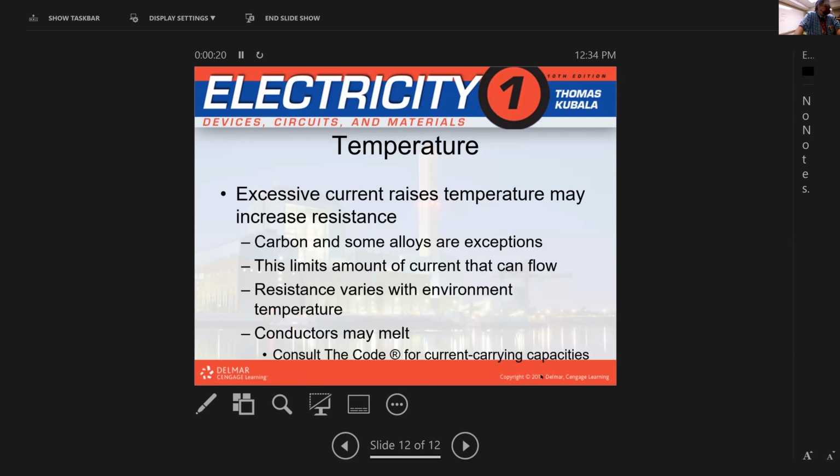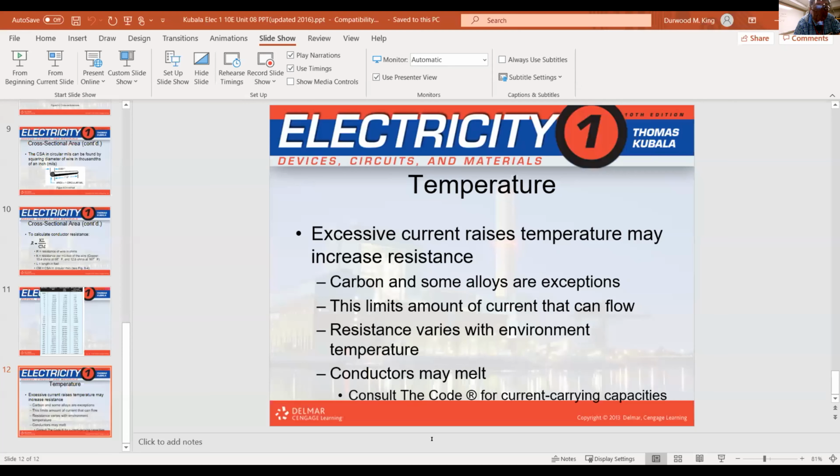Somebody was trying to use a number 10 wire for a 50 amp welder or 50 amp pressure washer. Somebody on the hog farm is trying to use a 50 amp pressure washer through a number 10 wire. And the number 10 wire, if you look on that chart, what do you see for the amp rating? Let's just use that for an example. Let's actually look at that.